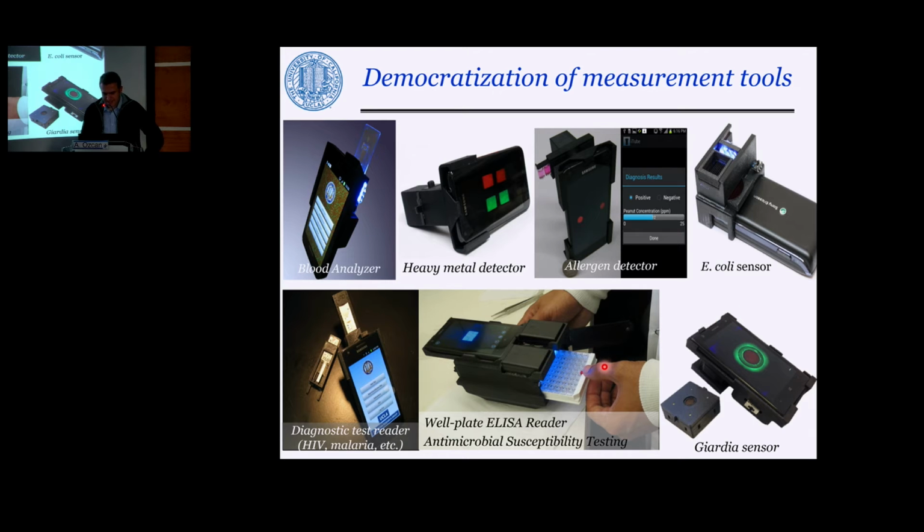This one is an ELISA plate reader. Some of you, at least, I know, must be using high-throughput screening formats like 96-well plates. This was actually an ELISA test reader to read 96-well plates. Without any mechanical components, in a single snapshot, you can have all the 96 wells to be imaged with a fiber optic system within that enclosure here. It works with fluorescence, chemiluminescence, and colorimetric assays.